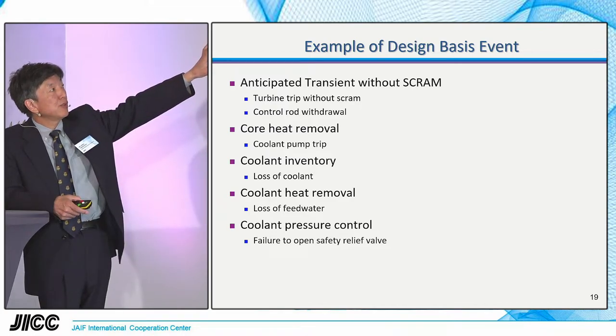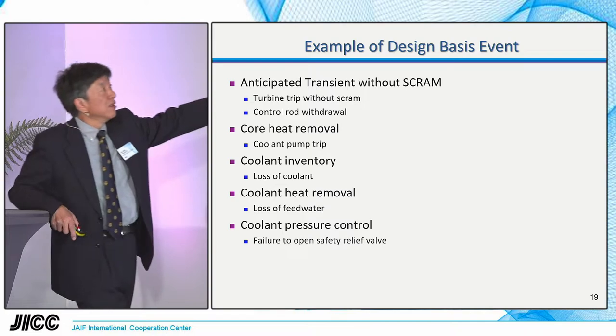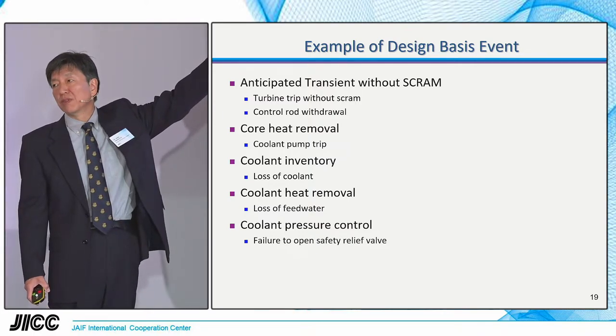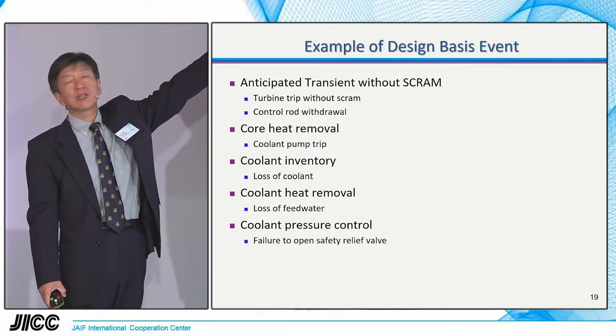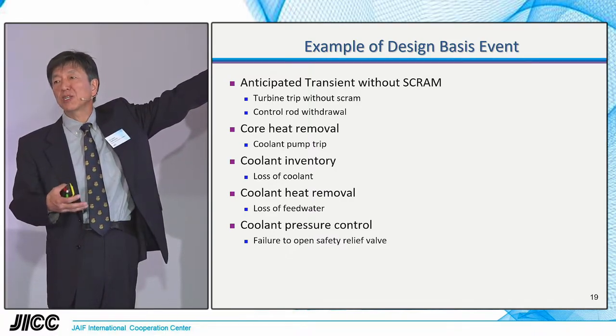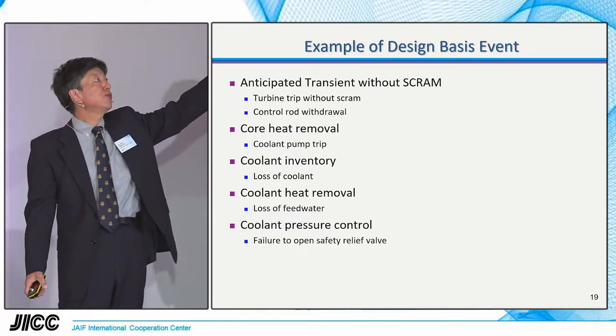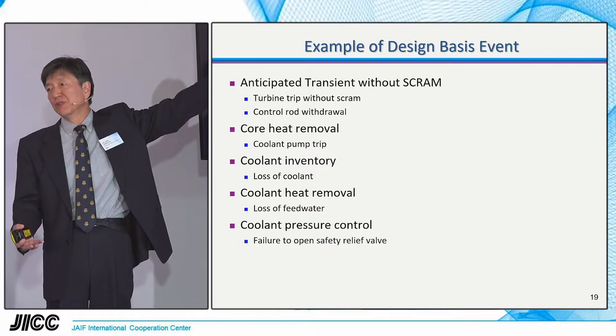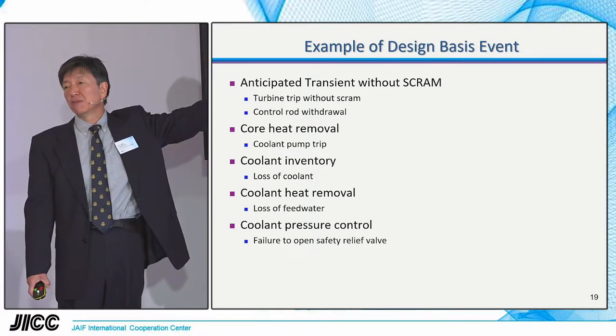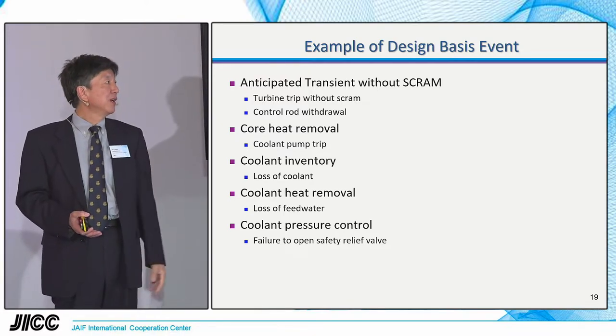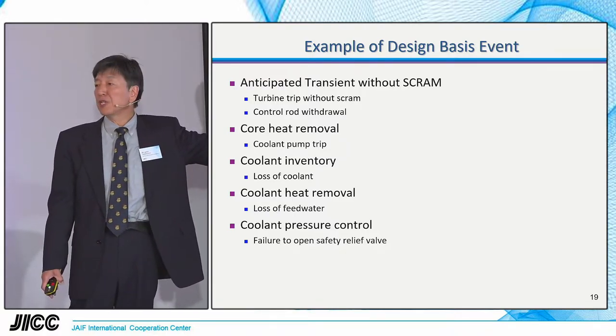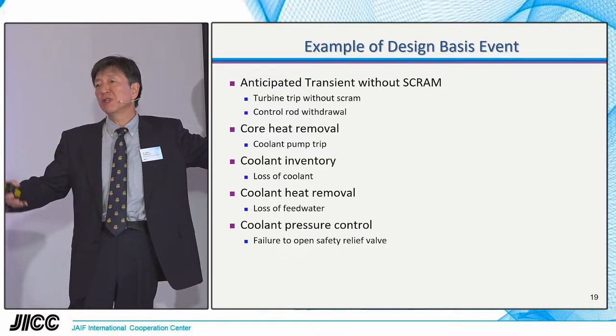We can now come to the definition of design basis events. For controlling power: anticipated transient without SCRAM is used for safety analysis; turbine trip without SCRAM or control rod withdrawal are examples of failure to control reactor power. For core heat removal: coolant pump trip is a good example. For coolant inventory: loss of coolant — pipe break — is an example. For pressure control: failure to open safety relief valve could escalate pressure.